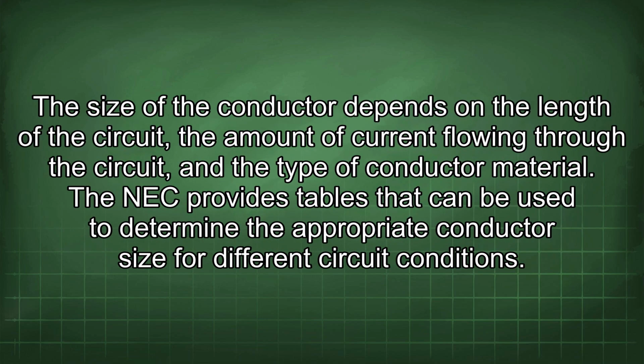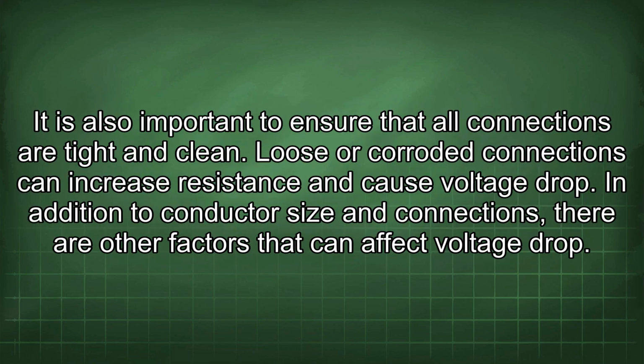The size of the conductor depends on the length of the circuit, the amount of current flowing through the circuit, and the type of conductor material. The NEC provides tables that can be used to determine the appropriate conductor size for different circuit conditions. It is also important to ensure that all connections are tight and clean. Loose or corroded connections can increase resistance and cause voltage drop.